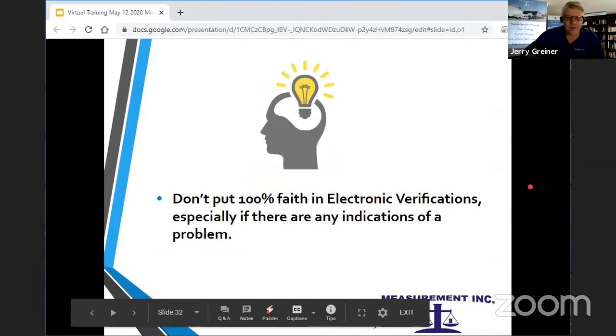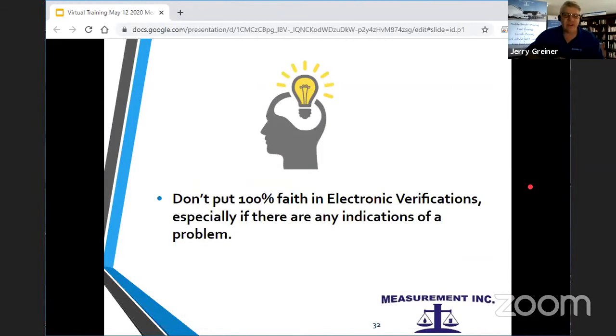So we learned from that: don't put 100% of your faith in the electronic verifications, especially if there are indications of a problem. Don't trust the electronic verification, because although they work in a lot of cases, on this one they didn't work. The manufacturer told us that the newer version of the software should have picked that up. This is a 2018 meter, so we don't have a lot of meters in the field with the newer version of the software yet. The newer version came out in 2019 and would probably pick that up. But like I said, it's not always there.